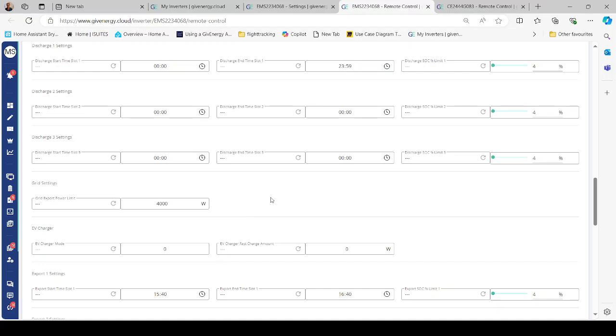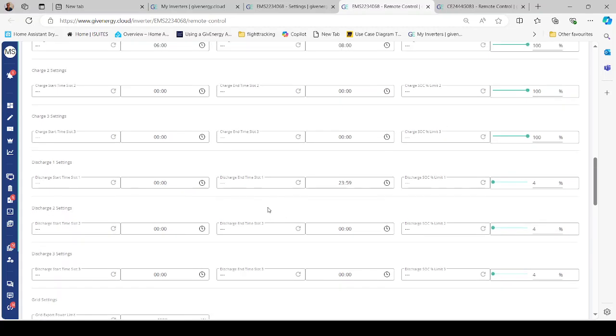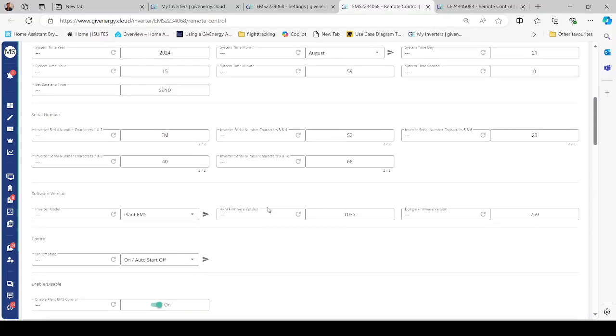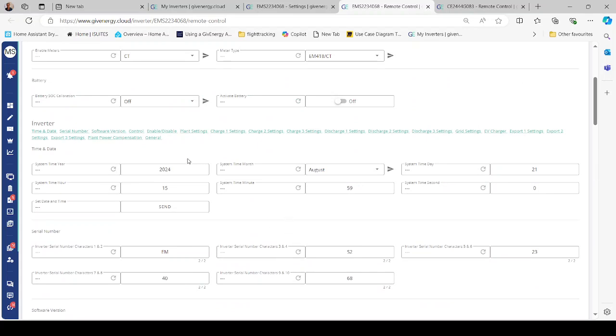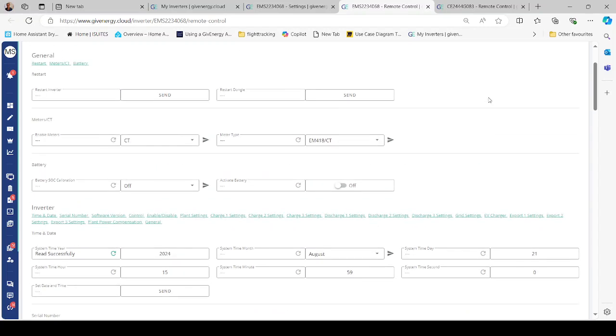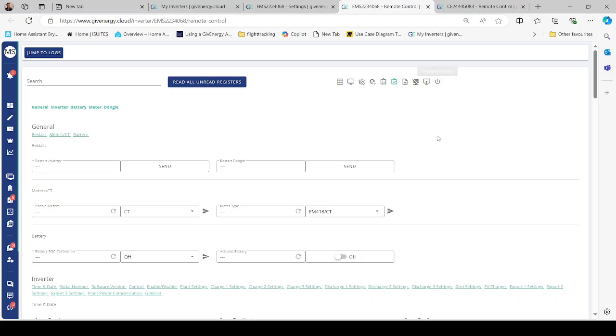One of the other issues you may find is if your inverter is showing error and the customer says it is flashing red then green, it's because the time has not been set or there has been a substantial power cut and they have lost the time settings. So just check here. And if you press the refresh button, it should come back with the same date. If it does not, if it comes back with 2017 or 2020, just repress the send button to reset the time, and then the EMS will start to run again. You will have to do a restart of the EMS. If you go to here and then just restart the inverter, and that will solve that problem.